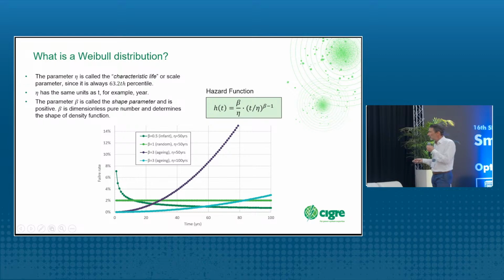If it's bigger than 1, here as an example, beta equals 3, then you have such an increasing failure rate with age, and this is of course a sign of aging. So, if you now investigate when transformers fail and you use this statistical data to plot the curve, and then you fit these data with such a Weibull distribution, and your beta is 1, then you know it's more or less random failures. If beta is bigger than 1, then you have aging behavior in your equipment. Of course, both happen. So you have random failures, you have infant failures, and you also have aging failures. So let's say 3 different distributions show the full failure processes.